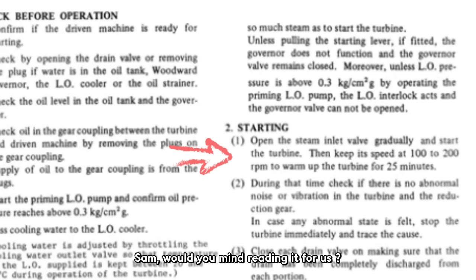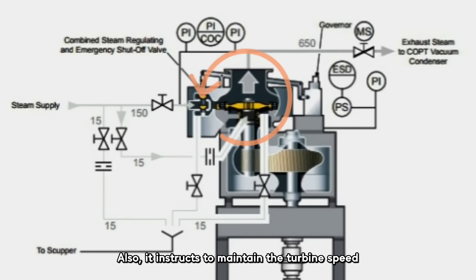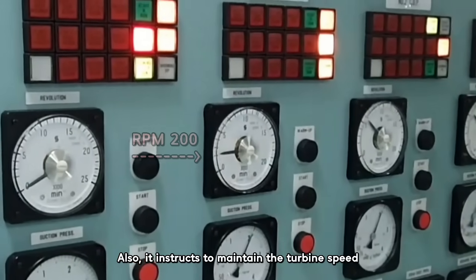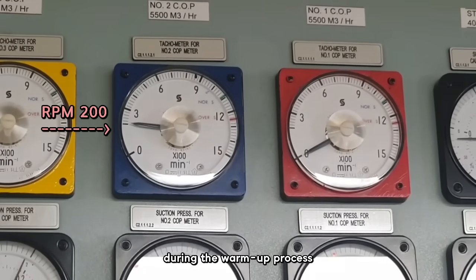Sam, would you mind reading it for us? Open the steam inlet valve gradually and start the turbine. Then keep its speed at 100 to 200 RPM, warm up the turbine for 25 minutes. Basically, it says to slowly open the steam inlet valve to start the turbine, and to maintain the turbine speed between 100 and 200 RPM for about 25 minutes during the warm-up process.